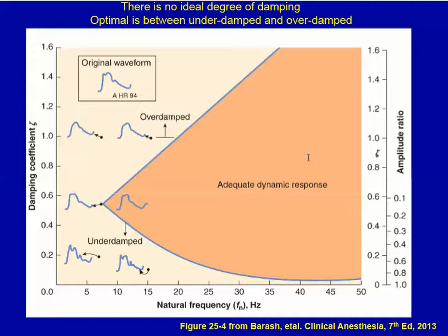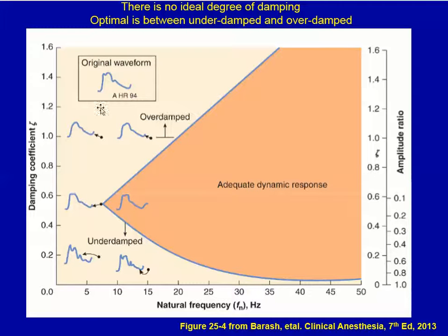This slide, taken from the latest edition of Barash, shows the range of optimal damping, which is influenced by the natural frequency. If the damping coefficient is too low you get an under-damped system; if it's too high you get an over-damped system. This triangle identifies the proper damping coefficient for various natural frequencies.